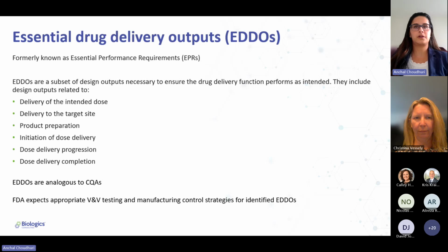So in terms of the delivery, the performance of the delivery device, FDA gives special consideration to what is now being called essential drug delivery outputs, or EDDOs. Draft guidance on this topic was just released on July 1st. And FDA has defined EDDOs as the design outputs necessary to ensure appropriate drug delivery. And these are outputs associated with dose delivery, delivery to the target site, preparation, initiation, progression, and completion of the dose delivery. And these are kind of analogous to CQAs in the drug world.